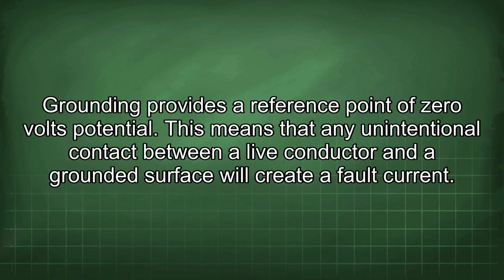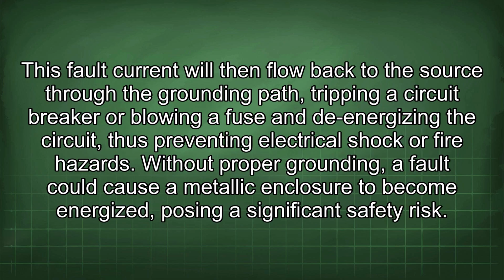Grounding provides a reference point of 0 volts potential. This means that any unintentional contact between a live conductor and a grounded surface will create a fault current. This fault current will then flow back to the source through the grounding path, tripping a circuit breaker or blowing a fuse and de-energizing the circuit, thus preventing electrical shock or fire hazards. Without proper grounding, a fault could cause a metallic enclosure to become energized, posing a significant safety risk.